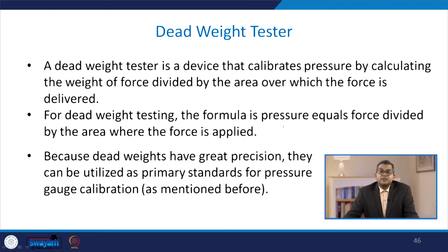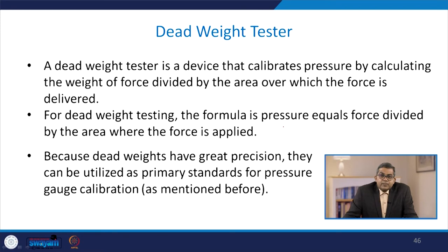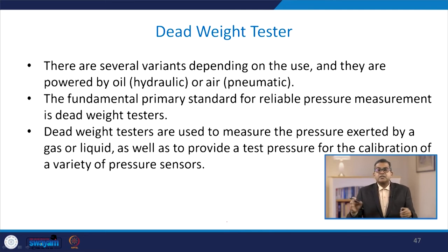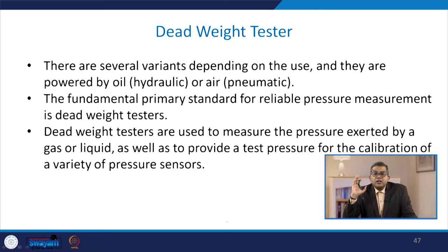A dead weight tester calibrates pressure by calculating the weight of force divided by the area over which the force is delivered: P = F/A. Because dead weights have great precision, they can be utilized as primary standards for pressure gauge calibration. There are several variants powered by oil (hydraulic) or air (pneumatic). Dead weight testers are used to measure the pressure exerted by gas or liquid and to provide a test pressure for calibrating a variety of pressure sensors.